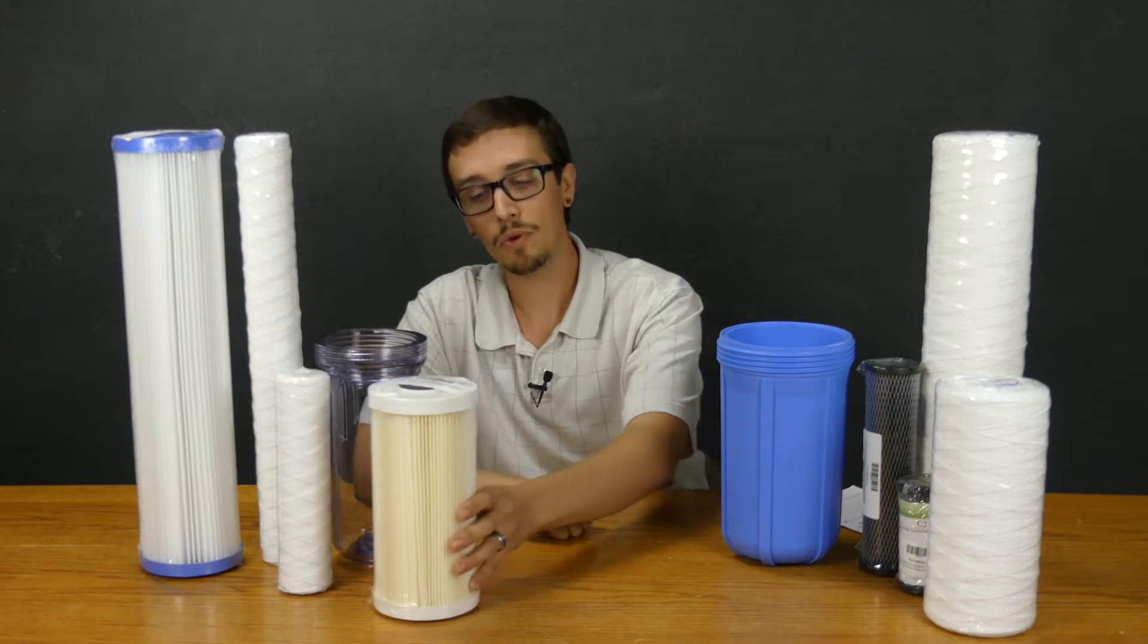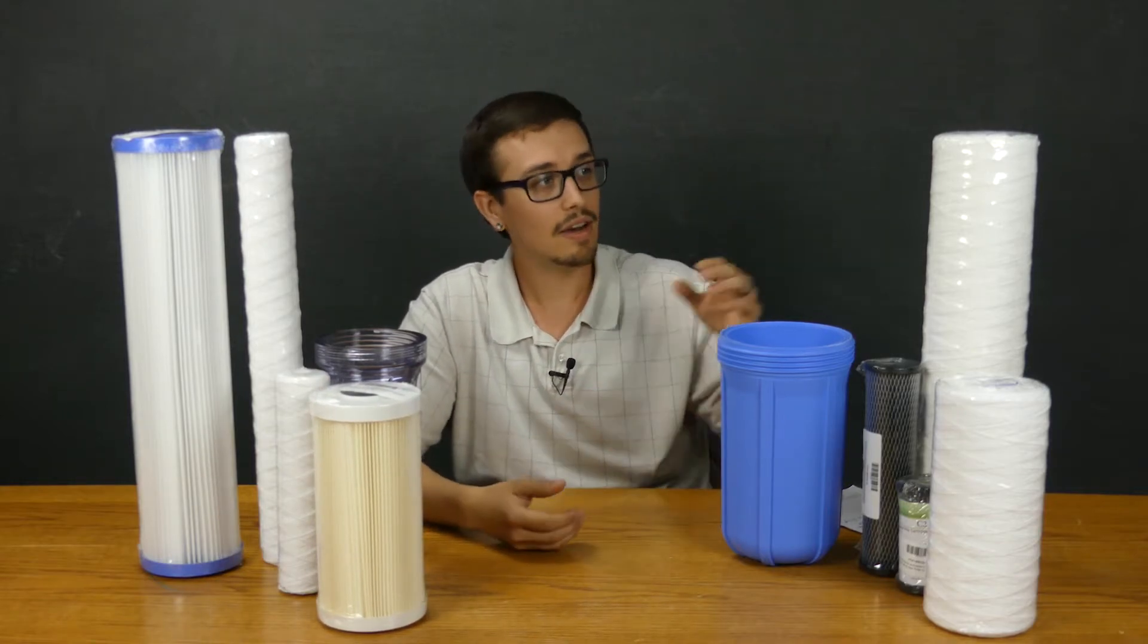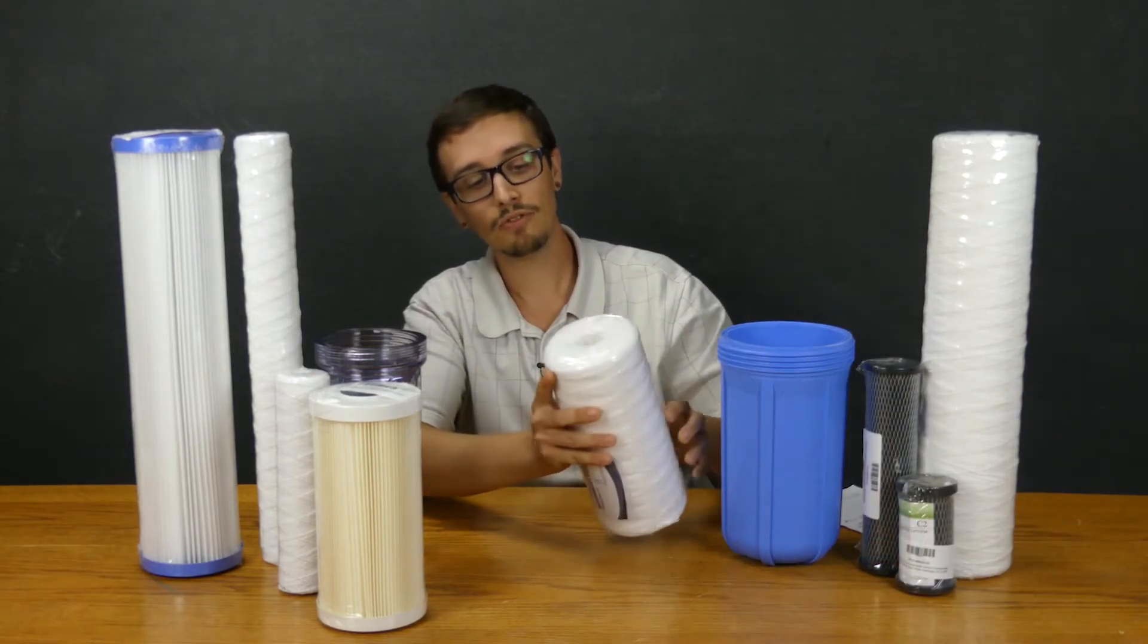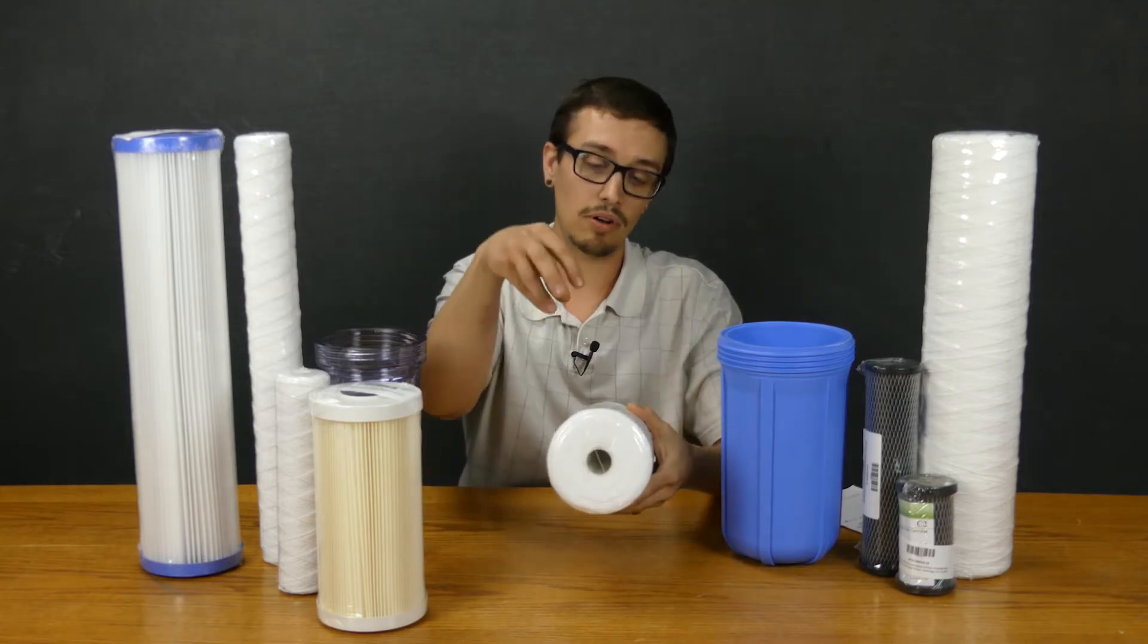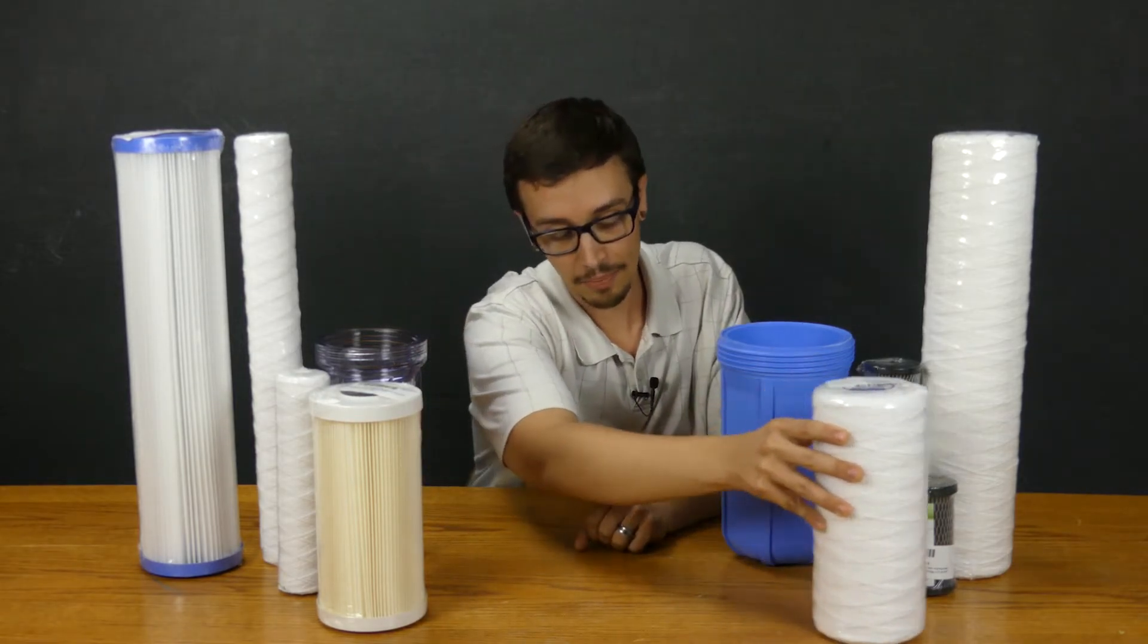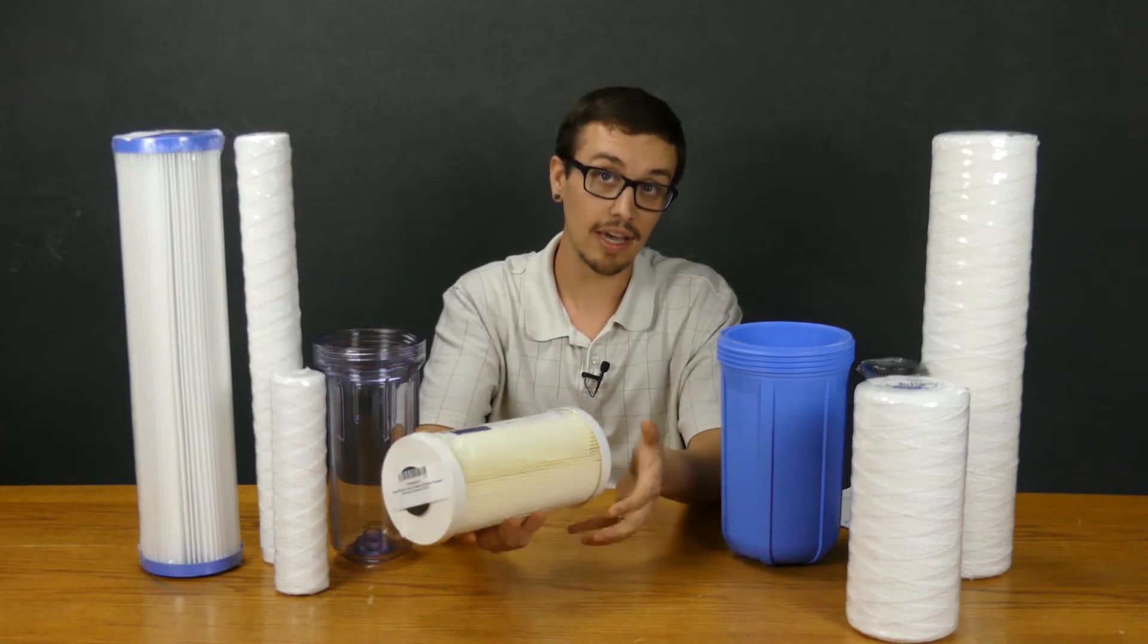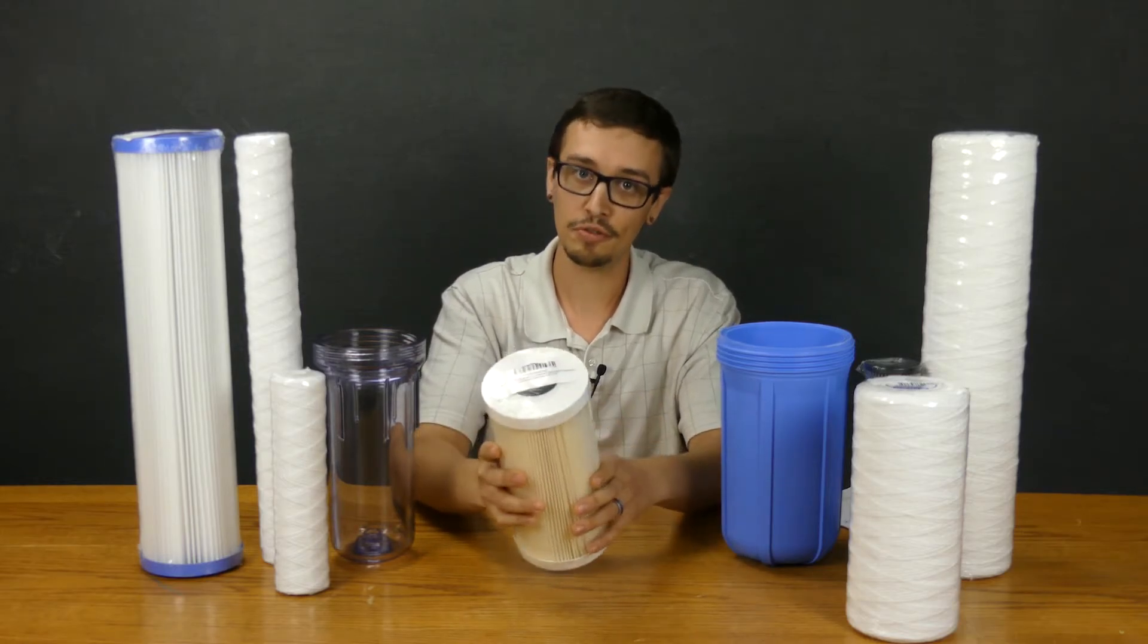The downside with pleated filters though is they don't have the density of these string type filters. If you look at a string filter, the string goes all the way through the body of the filter here. So the particles and sediment can weave their way in and really saturate and fill the filter up before it's completely shut off. Whereas with a pleated type filter, the surface is what you get. Once the surface is completely covered, it's time for a new filter.